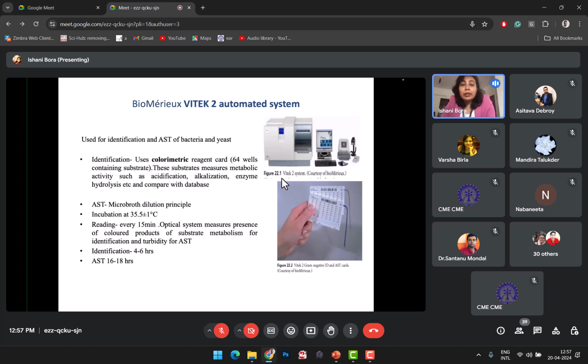It uses a colorimetric reagent card, which is a 64-well card where different substrates are added, and on the basis of this substrate analysis, the organisms are detected. Vitek has another advantage. The antibiotic sensitivity testing, AST, can also be done using a microbroth dilution principle. You can get the antibiotic sensitivity results in around 6 to 18 hours. So the advantages of Vitek are earlier identification of the organism, earlier issue of the antibiotic sensitivity report, and you can in fact get the MIC of the organism too. So bioMérieux has this system, Vitek 2.